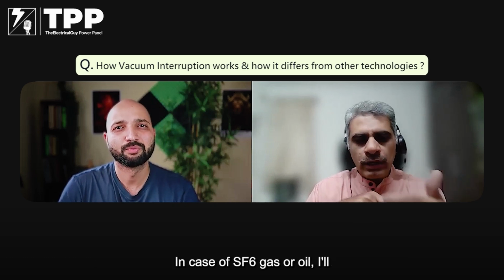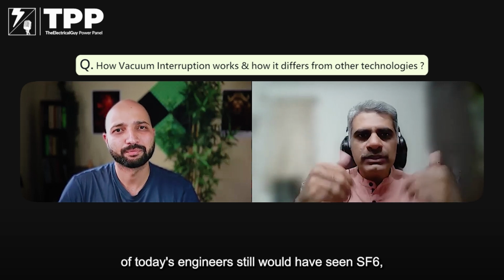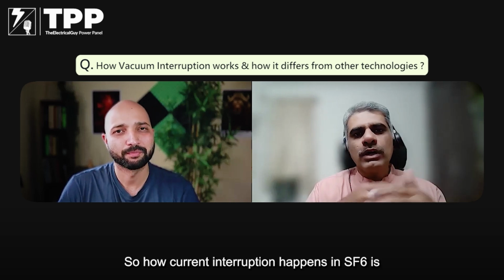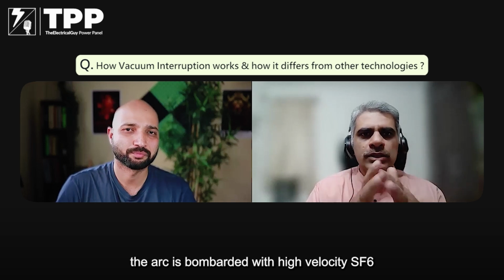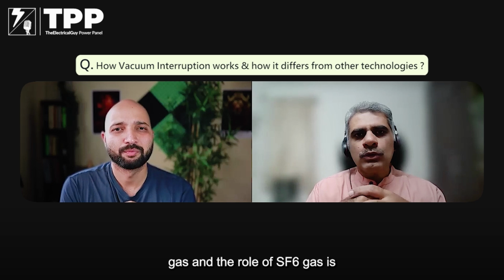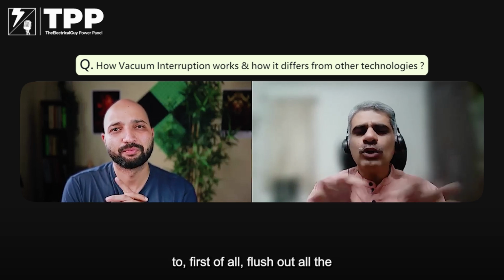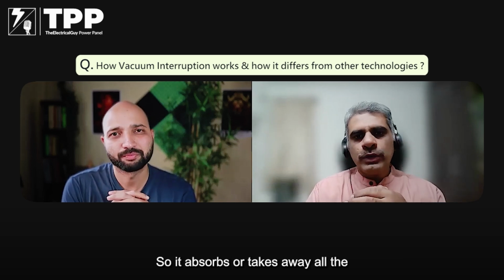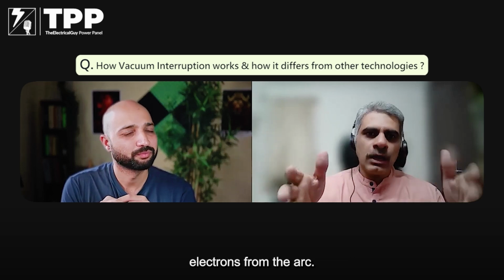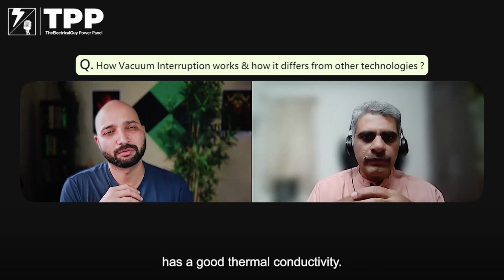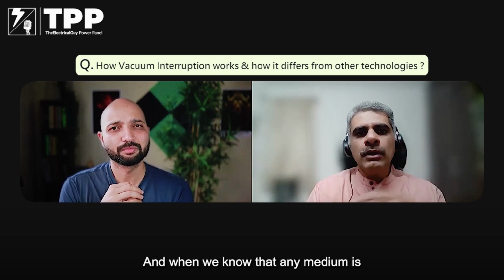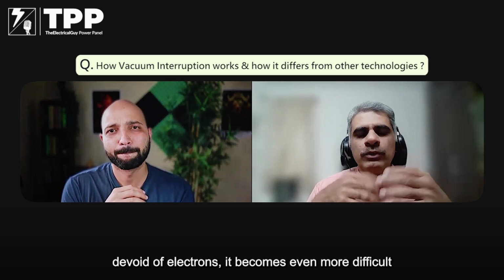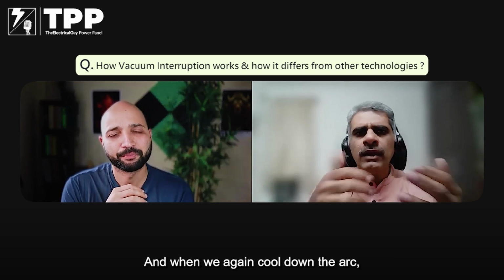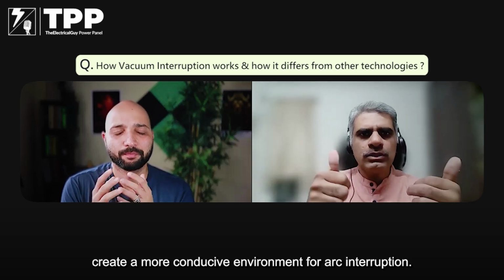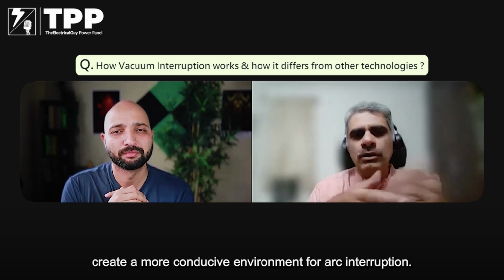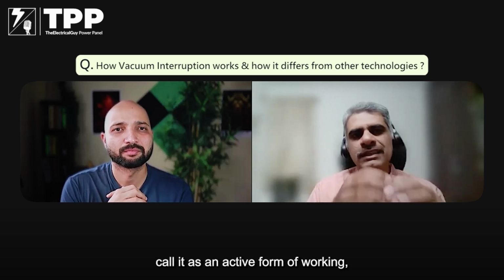In the case of SF6 gas or oil, I'll take the example of SF6 gas because many of today's engineers would have seen and learned SF6. Current interruption in SF6 happens as the arc is bombarded with high velocity SF6 gas. The role of SF6 gas is, first of all, to flush out all the electrons, because we know SF6 is an electronegative gas, so it absorbs or takes away all the electrons from the arc. Secondly, it cools the arc because SF6 gas has good thermal conductivity. When any medium is devoid of electrons, it becomes even more difficult for the arc to exist. And when we cool down the arc, its conductivity decreases and its resistance increases, again creating a more conducive environment for arc interruption. So this is how SF6 works, and I call it an active form of working.